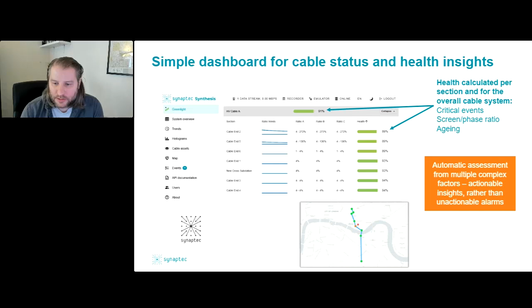Here we show an example of how a really simple metric, derived from measurements of phase current and screen current, can immediately highlight damage or an installation problem, such as something at a joint that was degraded, or maybe there was an initial installation problem that caused this issue. It could be that one of the steps in installing the joint was missed, and it had some impact later in terms of insulation quality or something similar.